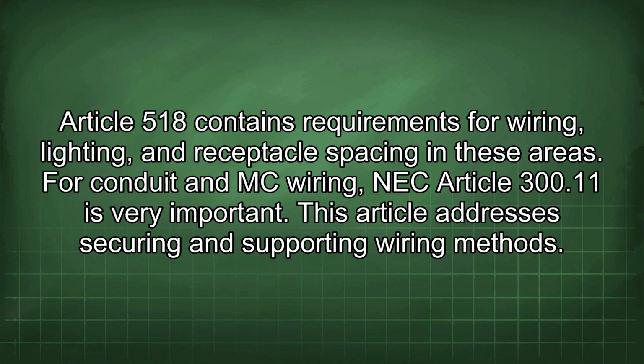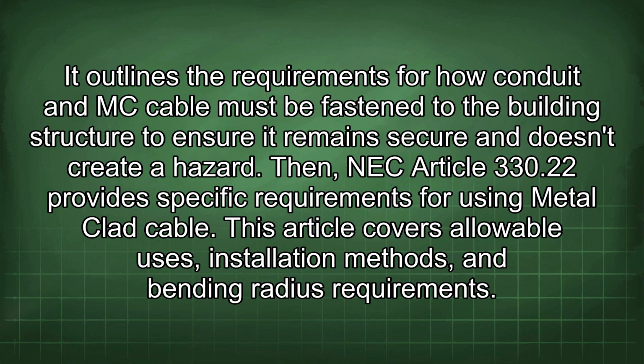For conduit and MC wiring, NEC Article 300.11 is very important. This article addresses securing and supporting wiring methods. It outlines the requirements for how conduit and MC cable must be fastened to the building structure to ensure it remains secure and doesn't create a hazard.